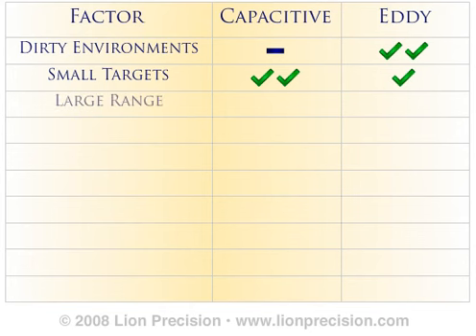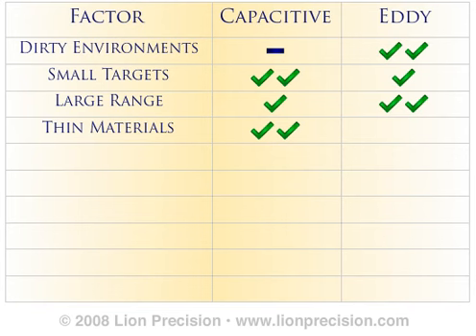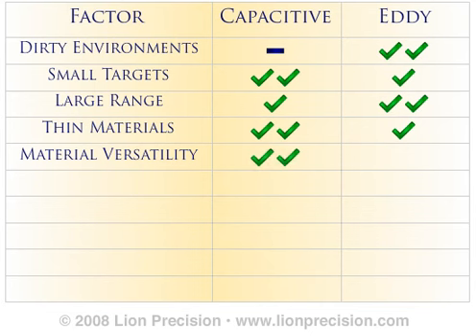For the same size capacitive or eddy current probe, the eddy current probe will have a larger measurement range. Because capacitive probes interact with the surface of the target, the material thickness is not a factor in capacitive measurements. Eddy current sensors have minimum target thickness requirements. Capacitive sensors have no sensitivity to the target material, provided it is conductive. Eddy current sensors are sensitive to material differences and must be calibrated to the application's target material.